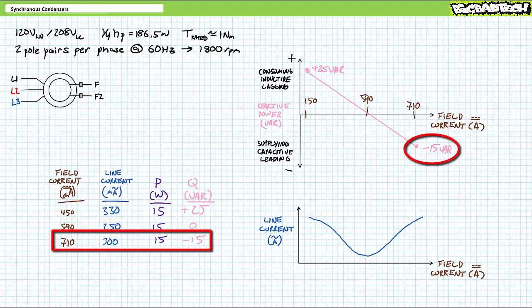On the other end, at a maximum field excitation current of 710 mA DC, the synchronous condenser draws 300 mA of line current per phase leading by around 45 degrees, consumes roughly 15 watts of real power to overcome friction, and supplies roughly negative 15 VARs. In this overexcited state, each winding appears to be capacitive in nature — this is the most negative reactive power each winding would be capable of supplying.